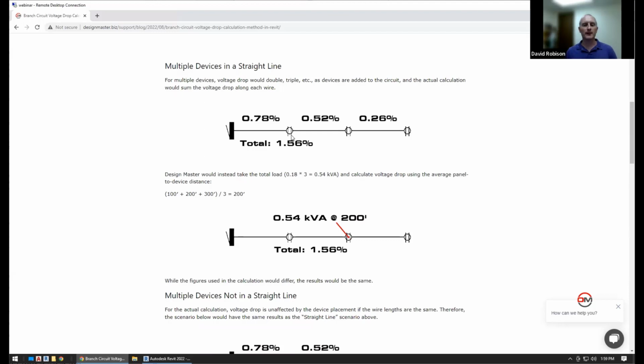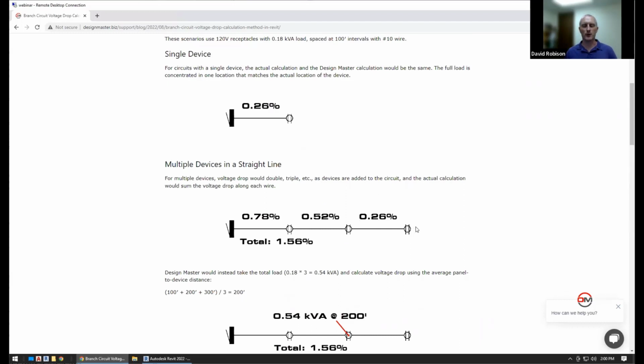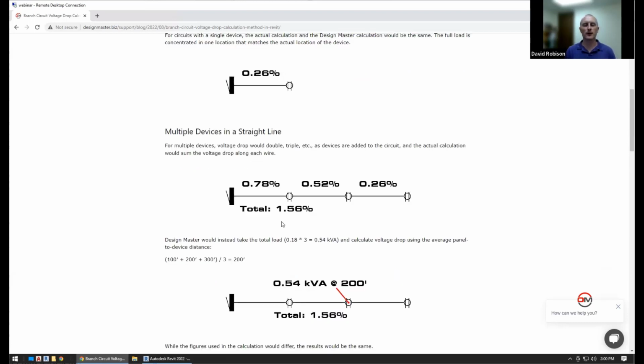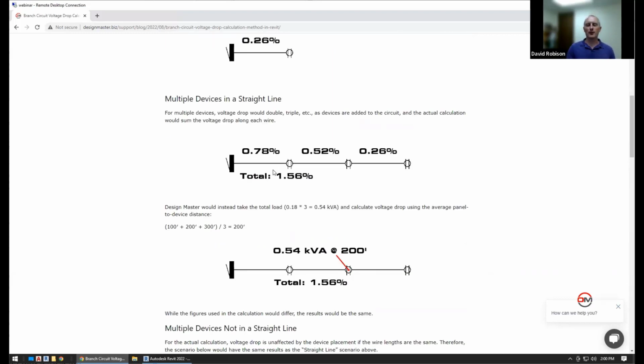So if we have three of these in a line, you have the distance changing. You also have the load changing because it's a little bit tricky what's actually plugged into those receptacles. But assuming they each have 0.18 kVA on them, we're going to have three times that on this first receptacle. Here, we only have two times that. By the time we get down here, there's only one receptacle worth of load. So if you do the math, we've got 0.26 for this one here, and then double that for this part of the circuit, triple that here, and then you add all of those voltage drops up to get the total on this circuit. That would be the most precise way to do that calculation.